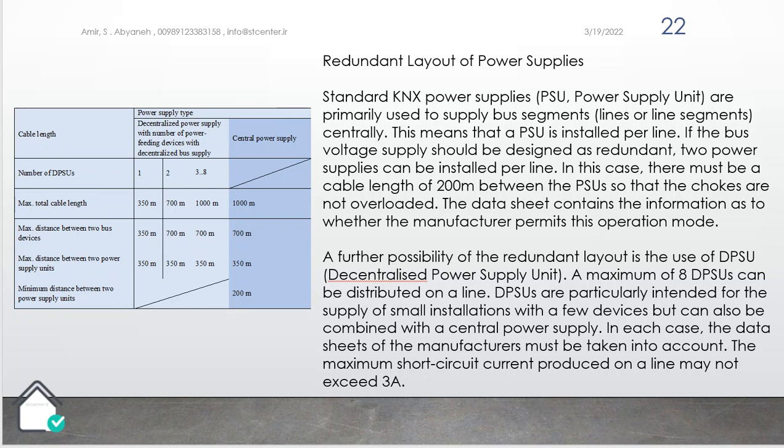You know, some devices in KNX have their own power supply unit. For example, the Synco 700 family product from Siemens to control the air handling units, boiler, and so on. Some of them provide us the decentralized power supply unit. So you can connect the device directly to the 230 volt AC, and this device can provide the power supply for KNX devices, like 2, 3, I don't know, according to the table in your installation chapter in the basic book.